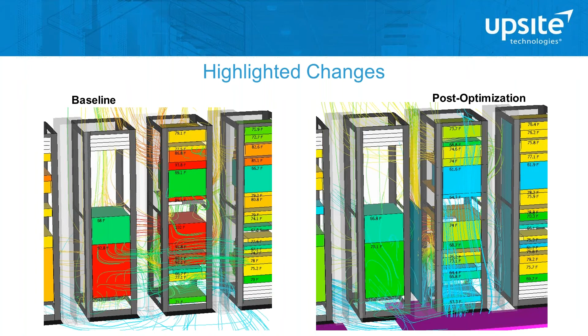Well, yeah, one thing to add there is that the concept of raising temperatures is a little bit controversial. It gets people pretty worked up. But there's a really important distinction to be made: the difference between raising the temperatures of the supply air or the intake temperatures of the IT equipment. A lot of people think that they're perfectly linked, that if you raise the supply temperature of the conditioned air, then you raise the intake temperature of the IT equipment. That's true if you don't make any changes in the computer room.